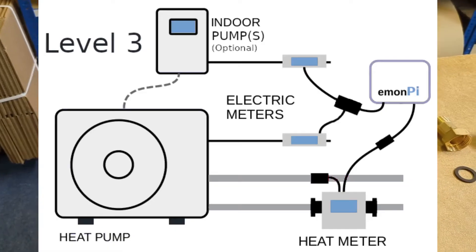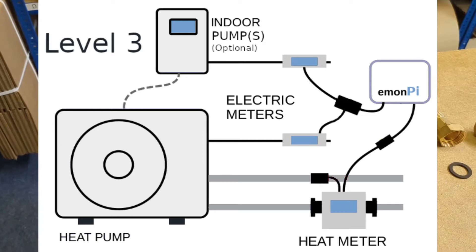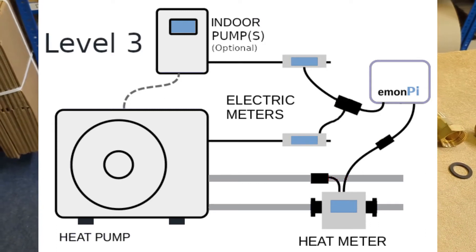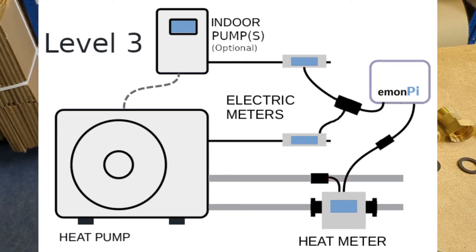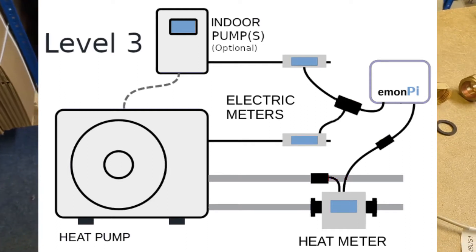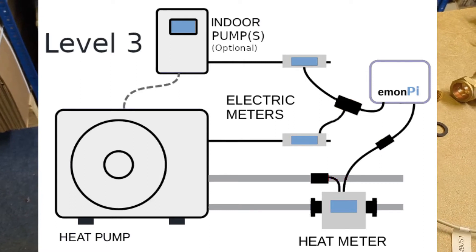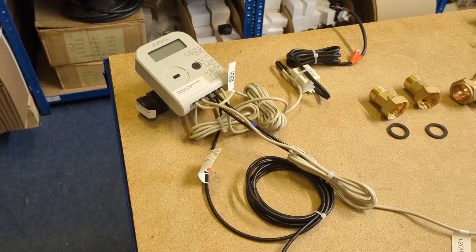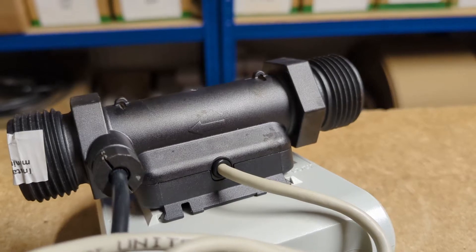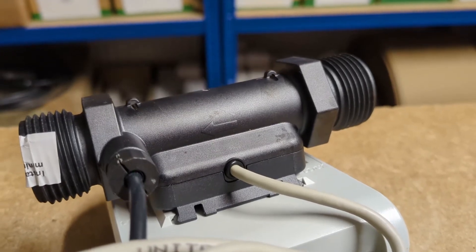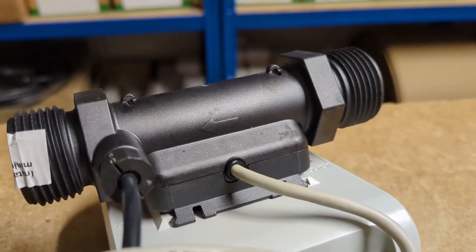By primary pipework, we mean the pipework going to the heat pump before any diverter valves on the flow and after any T's on the return, because we want to measure the full heat output from the heat pump for heating and hot water. Take care to orientate the heat meter following the direction of flow on the body of the meter.